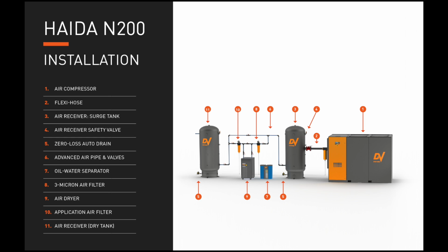Now Luke will discuss a typical installation of the Haida N200. Okay, so on the diagram to the right here, you can see the air compressor, the N200. These compressors also produce about 500,000 BTUs per hour. So that's the expelled heat coming out the top of the unit. So that can definitely be utilized within the facility.